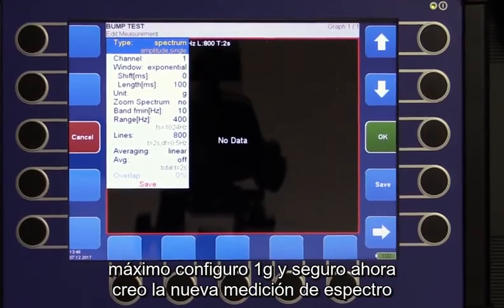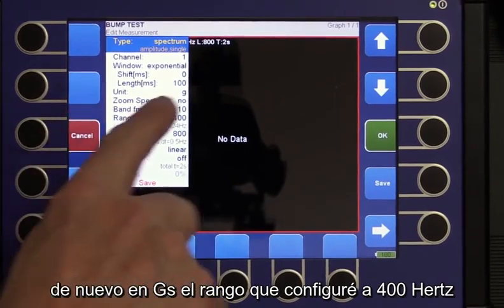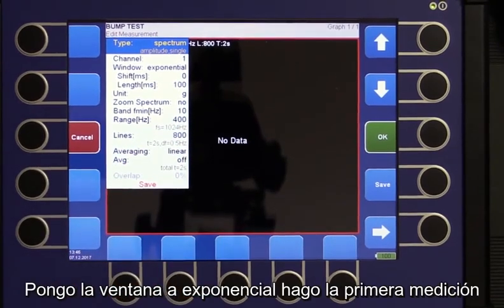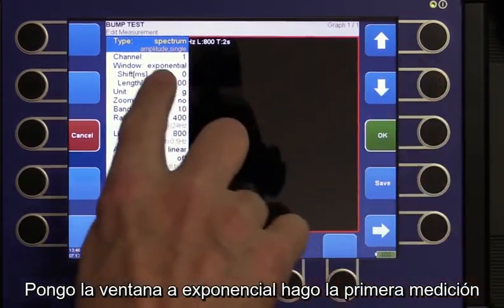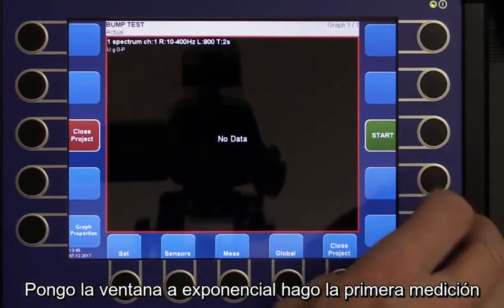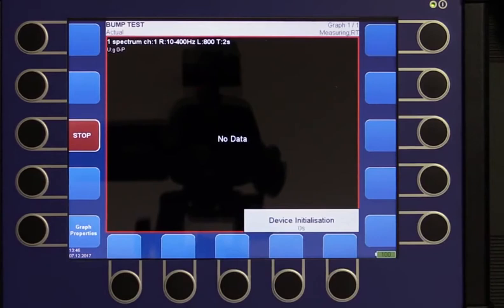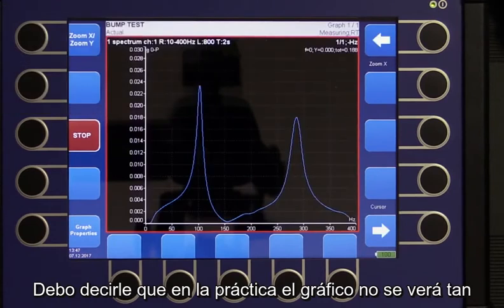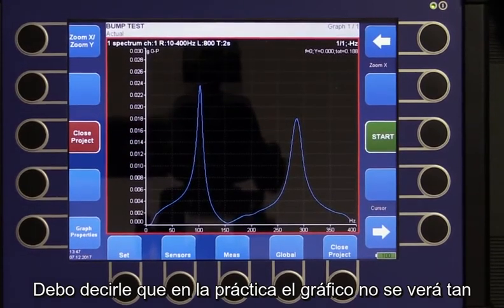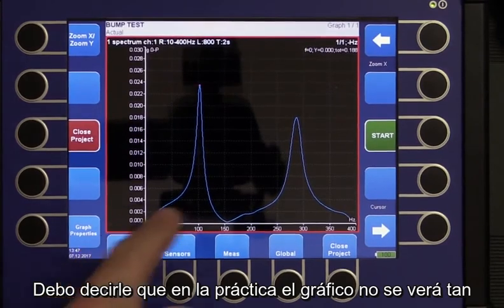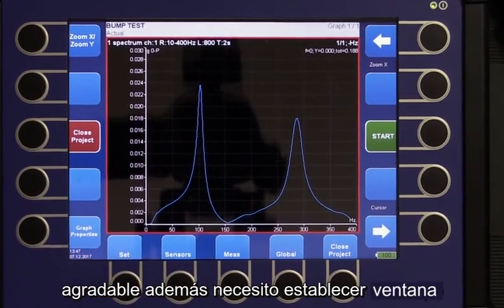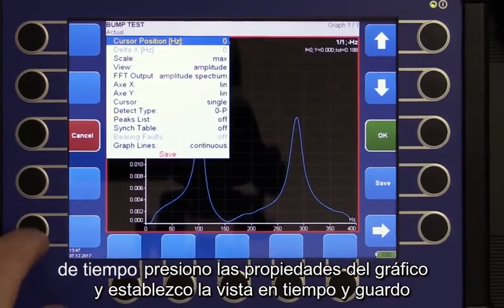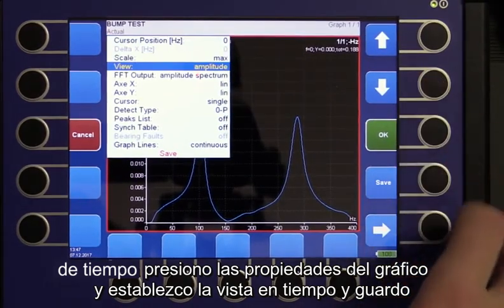Now I create a new spectrum measurement, again in G's. I set the range to 400 Hz and set the window to Exponential. I make the first measurement. I should mention that in practice the graph will not look so nice. Additionally, I need to set the time window — I press Graph Properties, set the view to Time, and save.